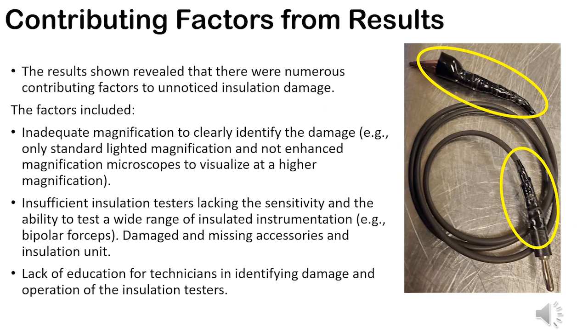So let's discuss the contributing factors from the study. The results shown revealed that there were numerous contributing factors to unnoticed insulation damage. The factors included inadequate magnification to clearly identify the damage. For example, they only had standard lighted magnification like a desktop, and not enhanced magnification microscopes to visualize at a higher magnification. To give you an idea, a desktop magnifier can range between 1.8 to 2 times the magnification. Enhanced inspection microscopes start at 10 times the magnification all the way to 230 times the magnification.